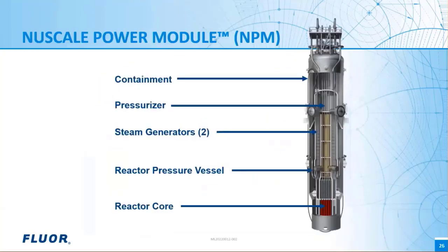The NuScale small modular reactor puts all of those same components in a single NuScale power module or NPM. The NuScale power module is an integral vessel that contains the reactor, two steam generators, the pressurizer, and those are all inside a containment vessel. The integral NuScale power module is about 15 feet in diameter and about 75 feet tall. There are no pumps. For comparison, the largest diameter pipe in the NuScale SMR is only 2 inches in diameter compared to that 30 inch that I just discussed.